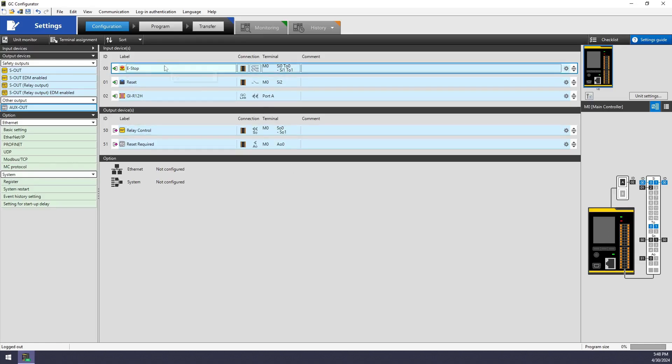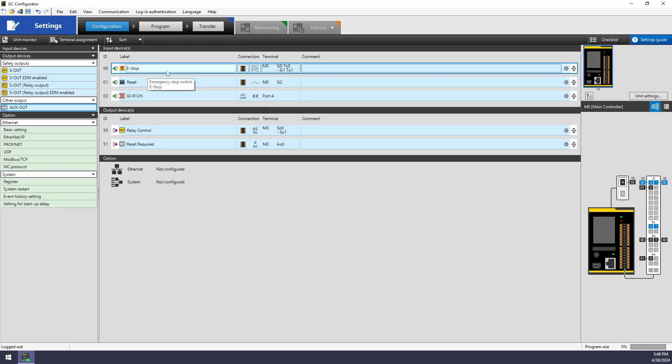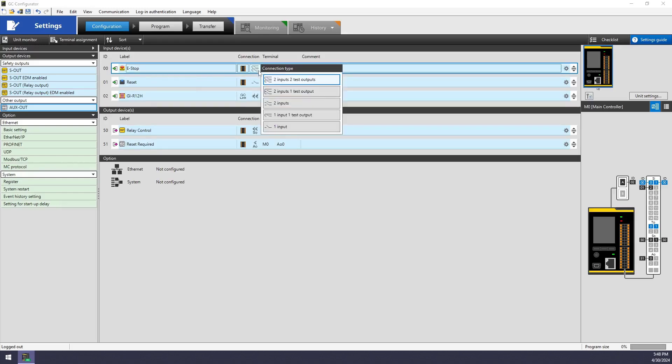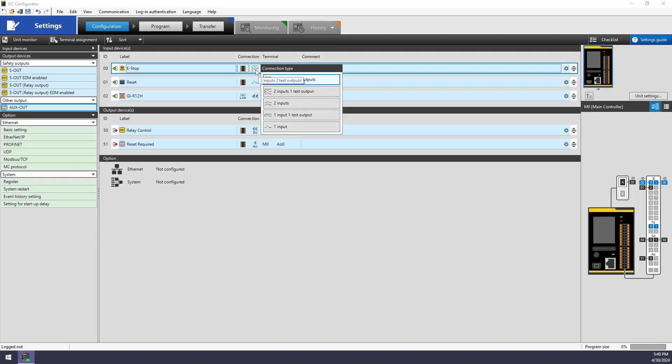The last thing I'll point out on the screen is that for the e-stop, for example, maybe I'm using a single channel versus a dual channel e-stop. Maybe I want to use test outputs versus 24 volts to source that e-stop. I can make all those selections here just by clicking on this icon.